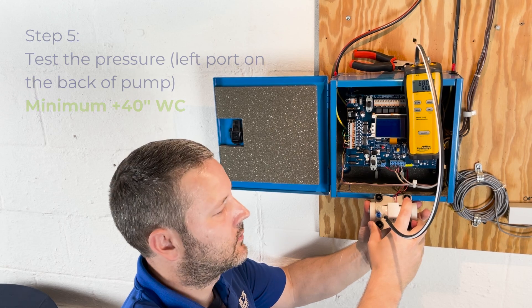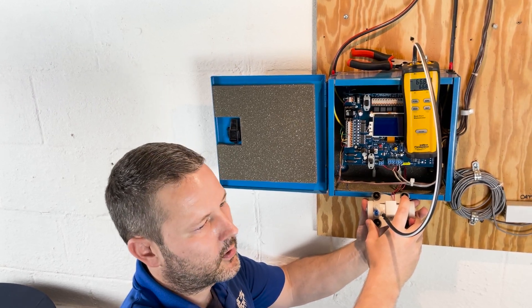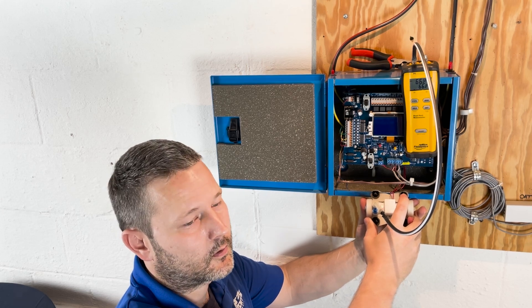48 inches on the vacuum side and 70 inches on the positive side — that's a good pump. That's our baseline, and that's what we're going to work with when we go to test the dampers and the solenoids.